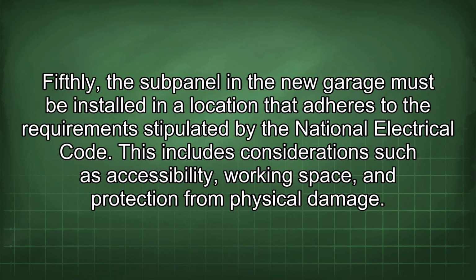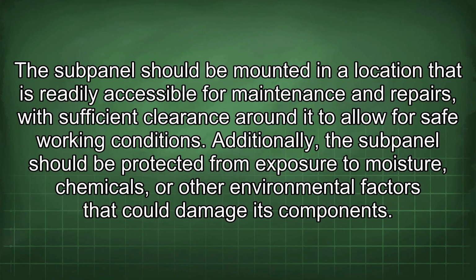Fifthly, the subpanel in the new garage must be installed in a location that adheres to the requirements stipulated by the National Electrical Code. This includes considerations such as accessibility, working space, and protection from physical damage. The subpanel should be mounted in a location that is readily accessible for maintenance and repairs, with sufficient clearance around it to allow for safe working conditions. Additionally, the subpanel should be protected from exposure to moisture, chemicals, or other environmental factors that could damage its components.